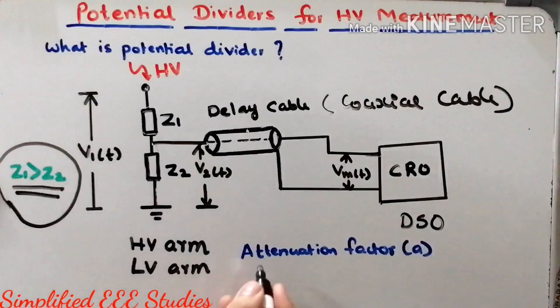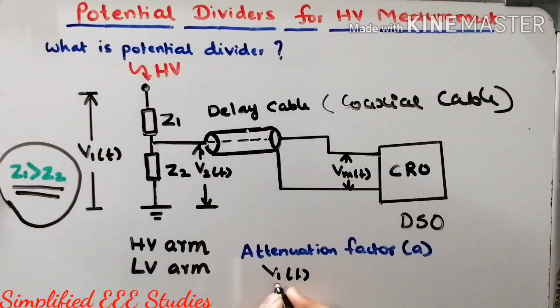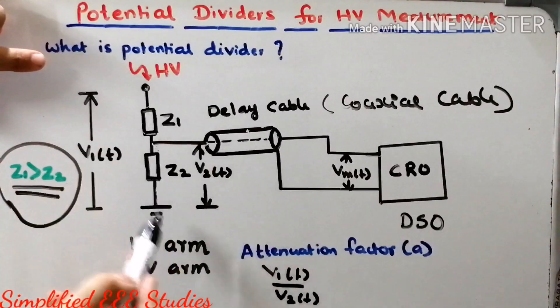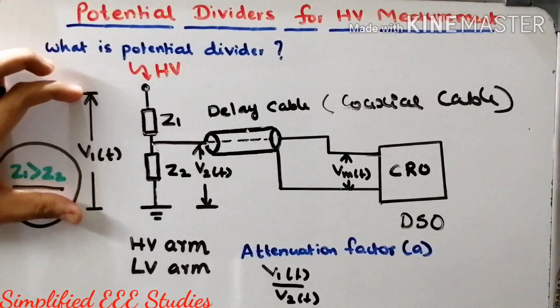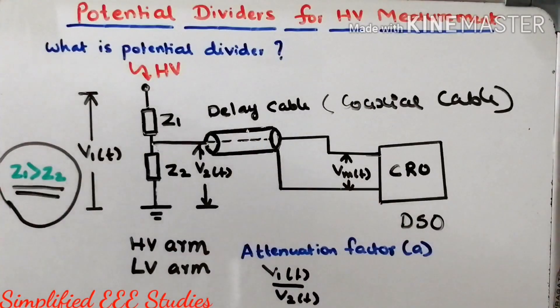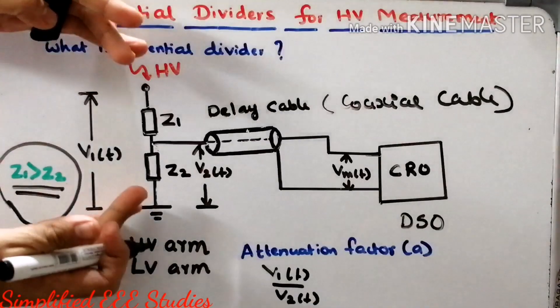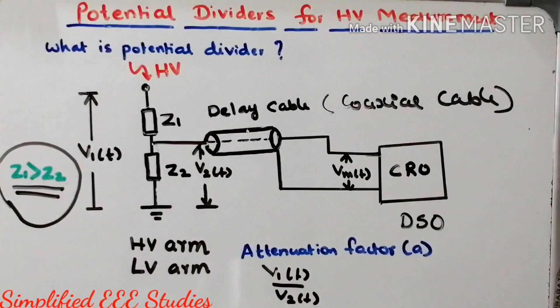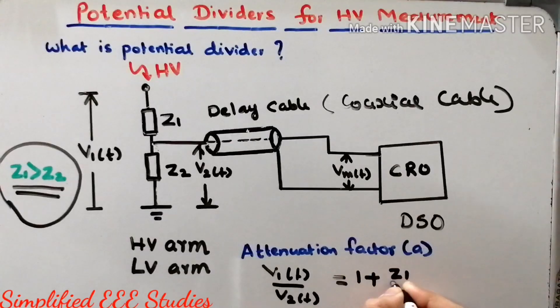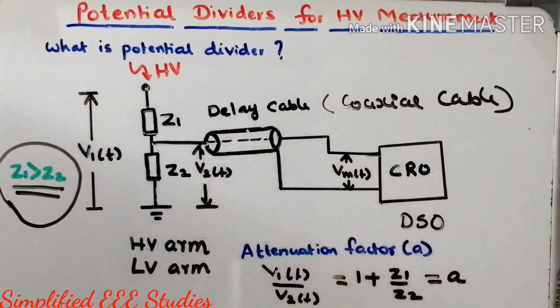While doing high voltage measurement using a potential divider, you need to consider one more term known as the attenuation factor. The attenuation factor is the ratio of V1 to V2, where V1 is the total voltage across the arm and V2 is the voltage across the low voltage arm. If you simplify this ratio, you get 1 plus Z1 divided by Z2. This quantity, 1 plus Z1 by Z2, is known as the attenuation factor, usually denoted by the letter A.